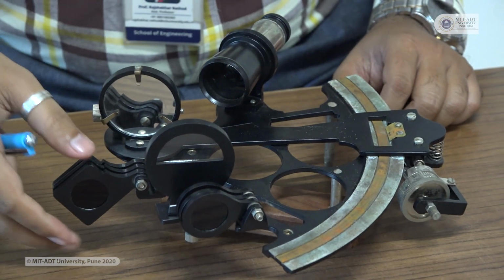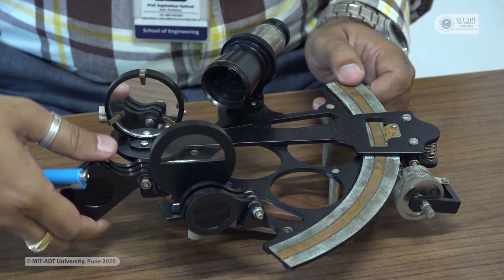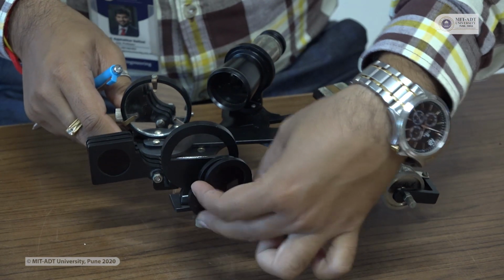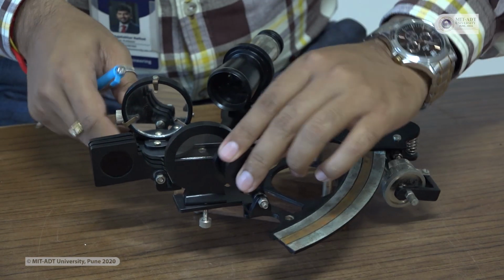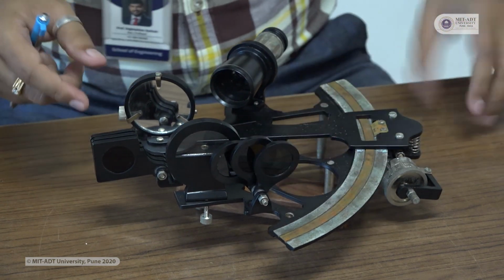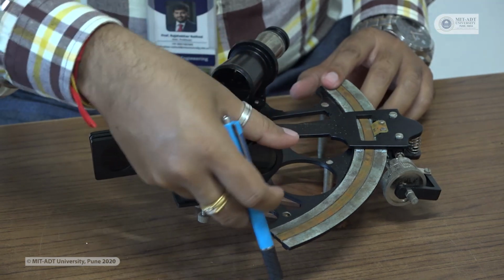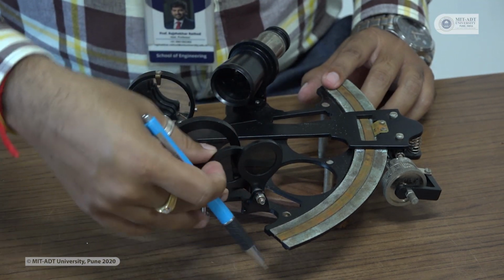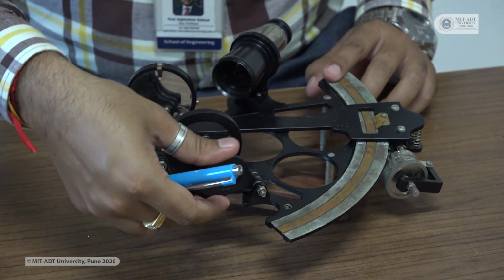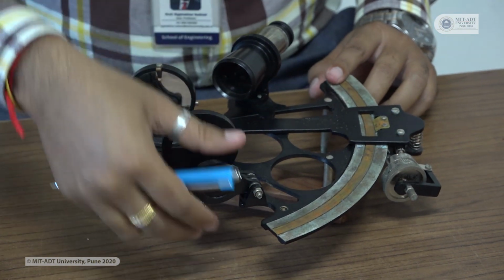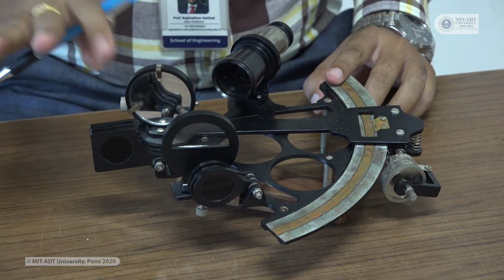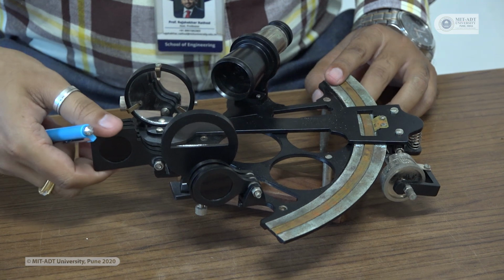Next, there are some shades for both the mirrors with different sizes. These shades are helpful when we operate the instrument in sunlight, because UV rays would strike your eyes through the plane mirror. So, we are using three different shades. If the intensity of UV rays is very high, then we use all three together. Mainly when you operate the instrument in sunlight. During night, it is not at all required. No shades are required.